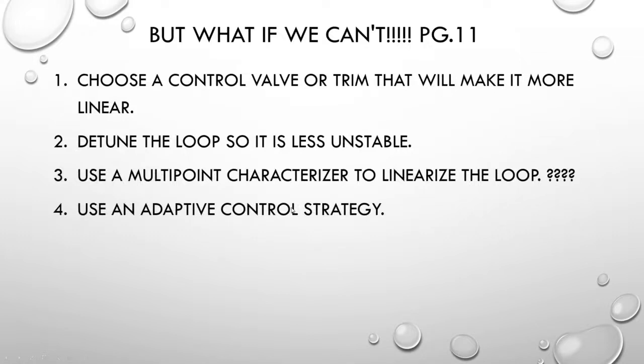If we can't stay in the same set point area, we have to do something. There are a few things we can do. First, we can choose a control valve or trim for that valve that will make it more linear, or at least opposite to the process non-linearities to straighten it out. The second option is to detune the loop so it is less unstable in operating ranges we're not normally in. If we're one day at 50% set point, another at 80%, another at 30%, that poses a problem — so we'll have to do something called detuning.